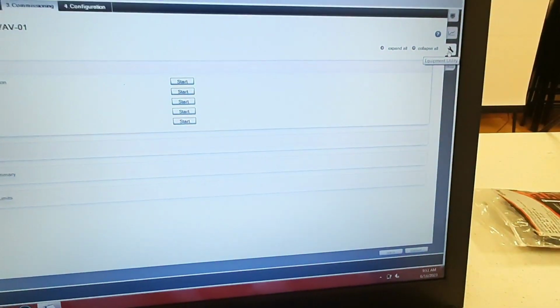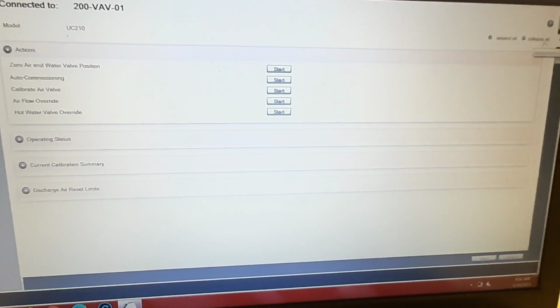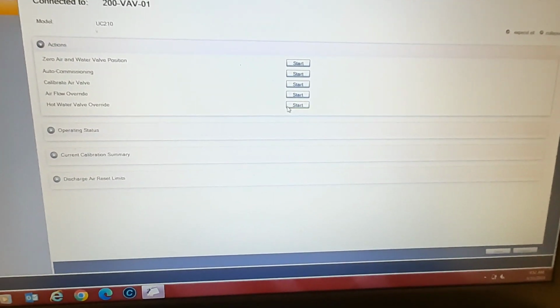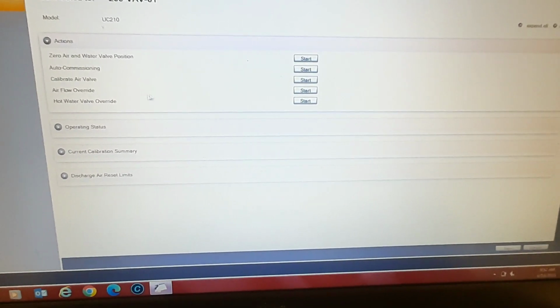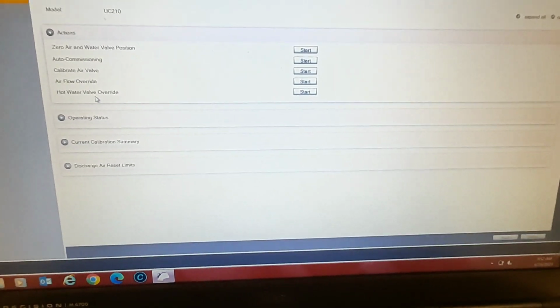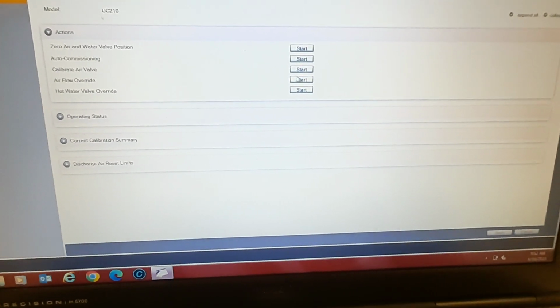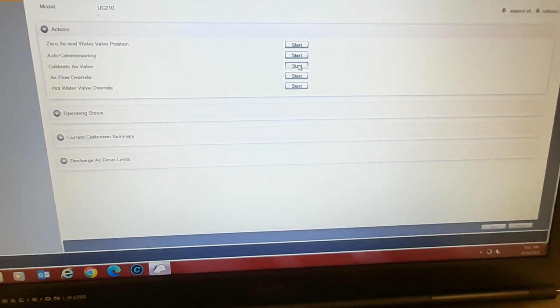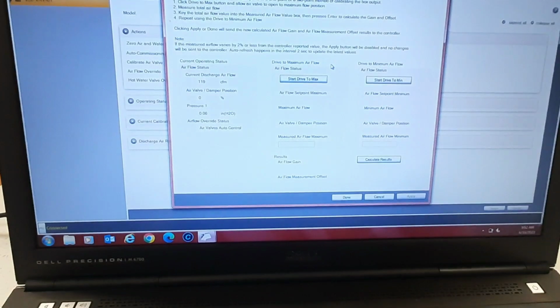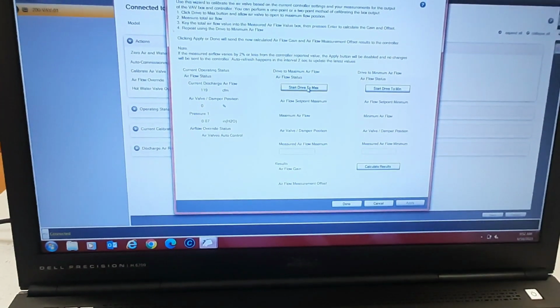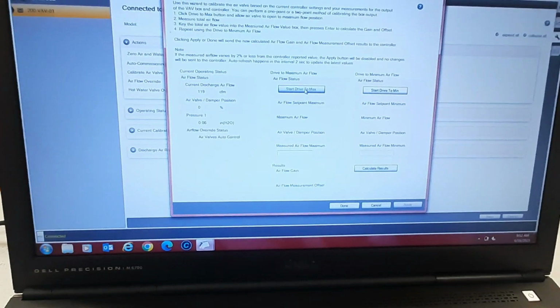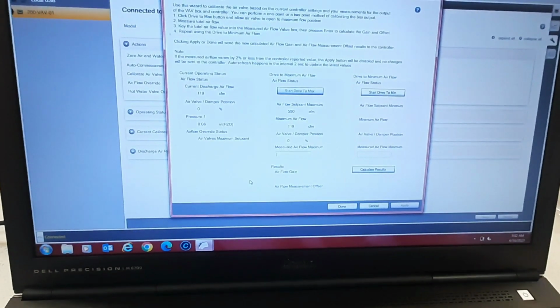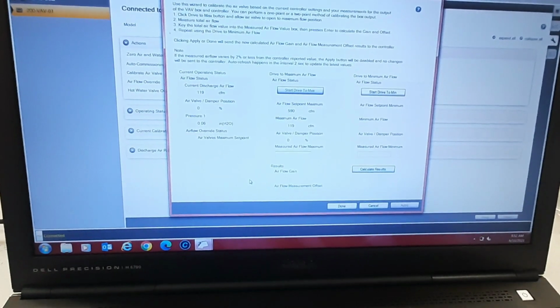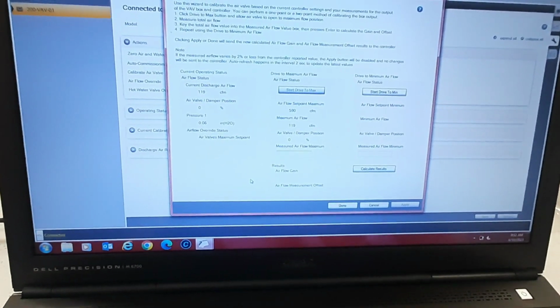It's not moving yet, so we're gonna try something different here. I'm in equipment utility, and I've got actions here to calibrate basically. So let's calibrate the air valve first and see what that does. Let's go start drive to max. Let's see if that will drive my valve.